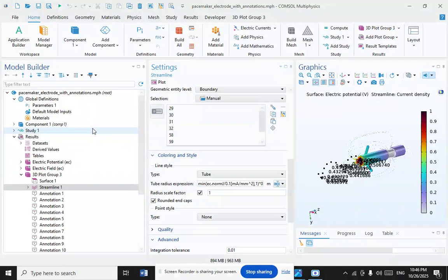And about threshold, the heart is composed of an excitable tissue, and an electrical pulse of a certain voltage is needed to capture the myocardium to make the heart function. The minimum voltage to achieve this is called the threshold. As this is a probabilistic property, the actual voltage used is higher than the threshold, usually by a 50 to 100% margin. Additionally, the electric pulse has a time component, and the proper description of the threshold is a voltage and pulse width. And all electrical circuits require a complete connection between the cathode and the anode.